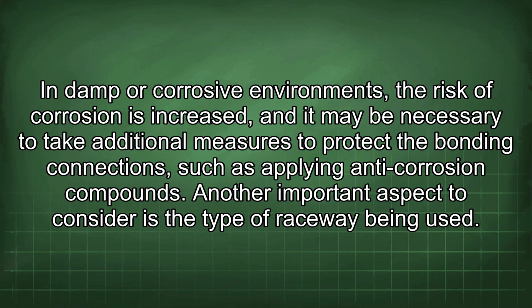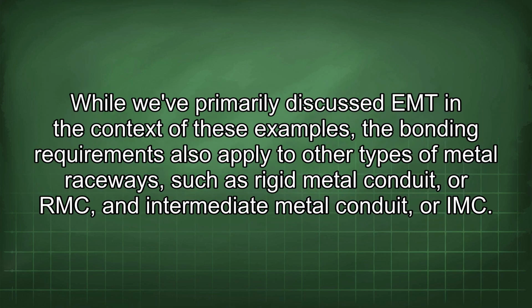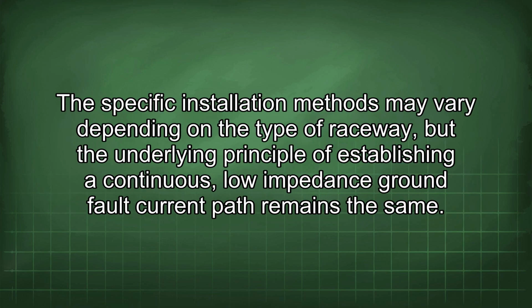Another important aspect to consider is the type of raceway being used. While we've primarily discussed EMT in the context of these examples, the bonding requirements also apply to other types of metal raceways, such as rigid metal conduit, or RMC, and intermediate metal conduit, or IMC. The specific installation methods may vary depending on the type of raceway, but the underlying principle of establishing a continuous, low-impedance ground fault current path remains the same.